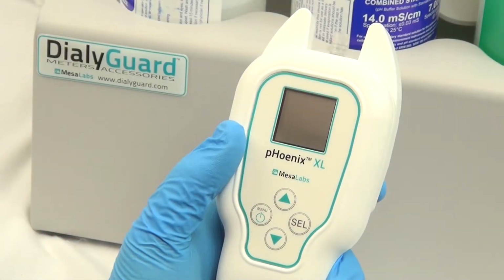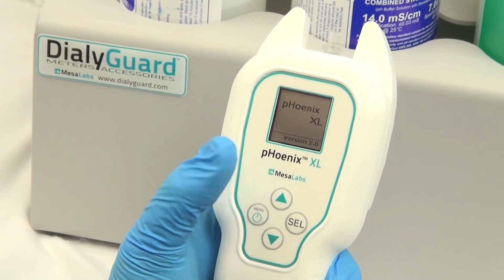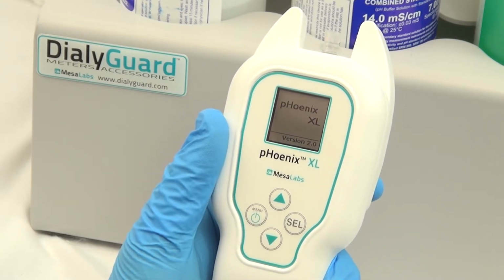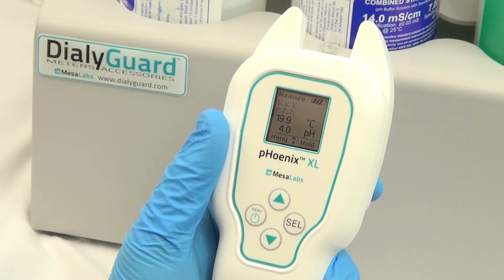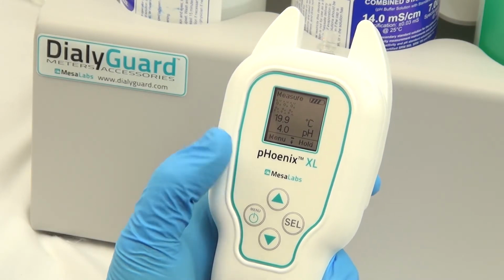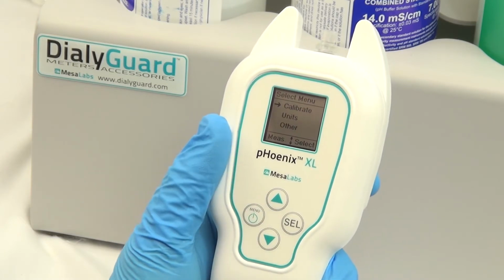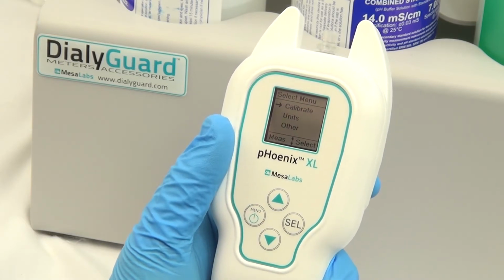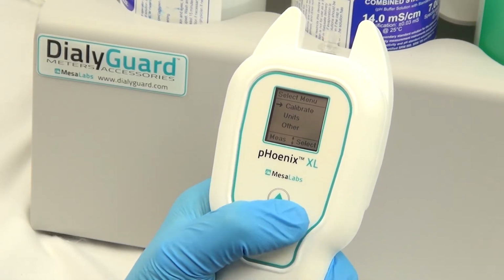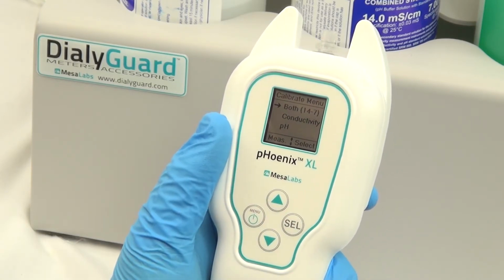First, take the pHoenix XL meter and turn it on by pressing and immediately releasing the power menu button. From the home screen, press the menu button, which will take you to a selection menu. Making sure the arrow is pointing to calibrate, press the SEL or select button. This will take you to the calibrate menu.